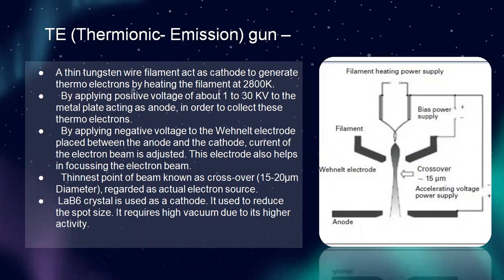First, the thermionic emission gun: a thin tungsten wire filament acts as cathode to generate thermoelectrons by heating the filament at 2800 K by applying a positive voltage of about 1 to 30 kV to a metal plate acting as anode to collect these thermoelectrons. By applying a negative voltage to the Wehnelt electrode placed between the anode and cathode, the current of the electron beam is adjusted. This electrode also helps in focusing the electron beam. The thinnest point of the beam, known as crossover, is 15 to 20 micrometers in diameter and is regarded as the actual electron source. A crystal is used as a cathode to reduce spot size. It requires high vacuum due to its higher activity. In the diagram: filament, base power supply, crossover of 15 micrometers, accelerating voltage power supply, anode, and Wehnelt electrode.